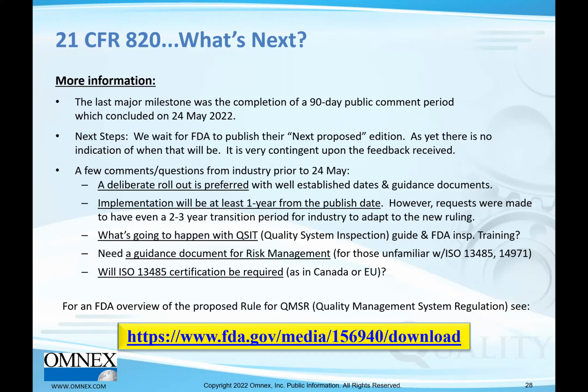Thanks, Lawson. One of our attendees said HLS, high level structure. Yes, that's the clause structure, 8 clauses versus the 10 clause structure of ISO documents. Is software needed to validate before using UDI? Not that I'm aware of. Let me put it this way, the UDI requirements came about before software requirements did. So no, you can do that via paperwork documentation.